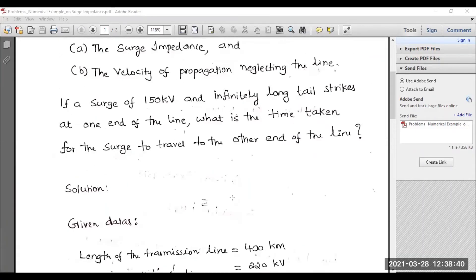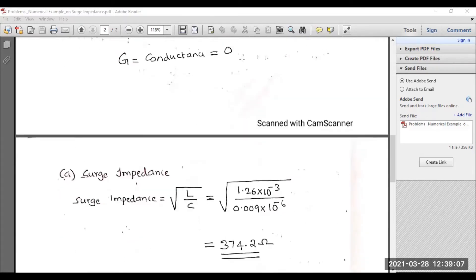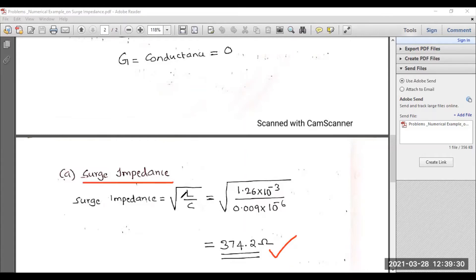Now I would like to calculate the surge impedance first. As you know, in transmission lines there is both capacitance and inductance, and the reactive power supplied by the capacitance equals the reactive power absorbed by the inductance. Based on that, the expression for surge impedance is Z naught equals square root of L divided by C. After substituting the values of L and C, the surge impedance equals 374.20 ohms.